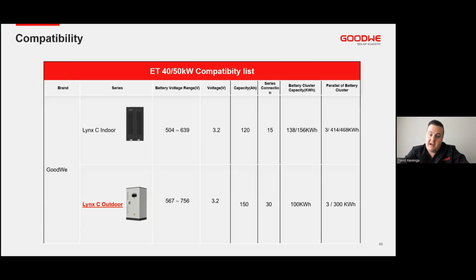Then the Lynx C Outdoor, a nice outdoor battery. It comes with an outdoor cabinet where the inverter can be installed in one section of the cabinet as well. You can also install the SDS in this cabinet, or alternatively, your SDS can be by a distribution board. These come in 100 kilowatt hour cabinets, so 0.5C discharge on these batteries, and you can have a maximum of 300 kilowatt hour batteries per inverter. That will give you your 300 kilowatt hours.